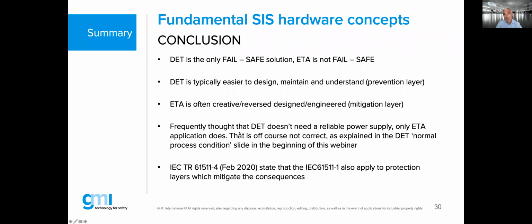Now, frequently taught, that was the poll question, is that de-energized to trip does not need a reliable power supply. Well, I can say, of course, that's not 100% correct. That's also why we have suitable power supplies with a systematic capability, as for instance GMI is also providing. And the last bullet here is the reference to report number 4, which is an informative section of the standard released in February 2020, clearly stating that it was often misunderstood that mitigation layers, in other words energized to activate, did not belong to the standard and did not have to be built in a reliable section. Well, now we can say that by the standard, it is also part that mitigation layers need to be built reliably.